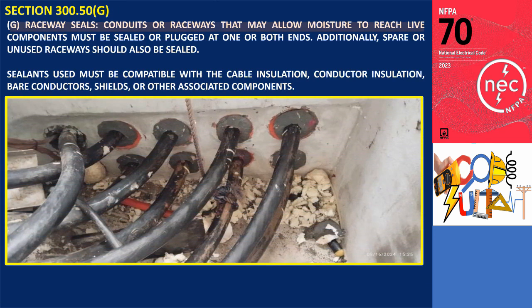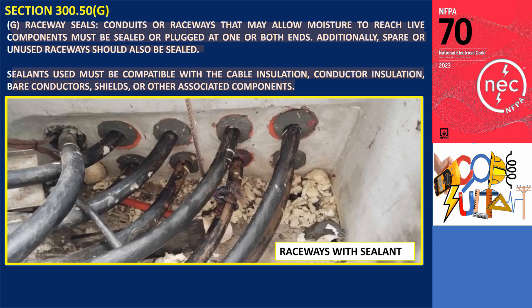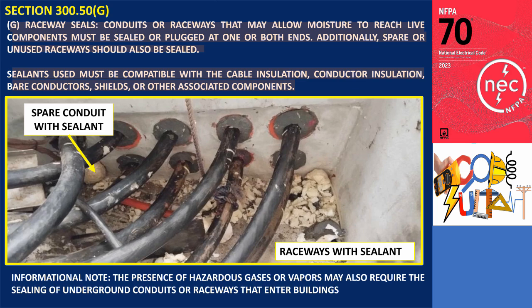Section 300.50(G), Raceway Seals: conduits or raceways that may allow moisture to reach live components must be sealed or plugged at one or both ends. Additionally, spare or unused raceways should also be sealed. Sealants used must be compatible with the cable insulation, conductor insulation, bare conductors, shields, or other associated components. The accompanying photo shows an underground installation where cables are housed in ducts, with sealant applied at the building entry point, and there is also a sealed spare raceway. Informational note: the presence of hazardous gases or vapors may also require the sealing of underground conduits or raceways that enter buildings.